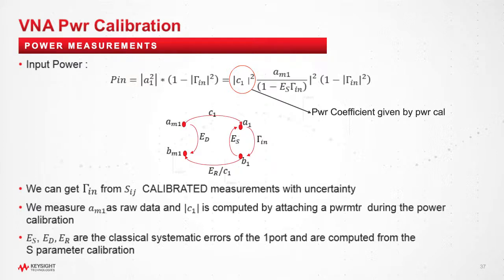Okay. What would be the sources of uncertainty for that? The sources of uncertainty are linked fundamentally to the model of the S parameter uncertainty that I showed you. So you will always have calibration, repeatability, and noise. You may have other causes, but those are the three main big players.